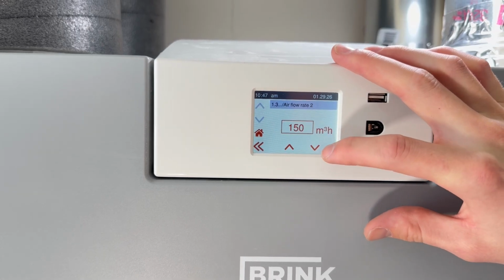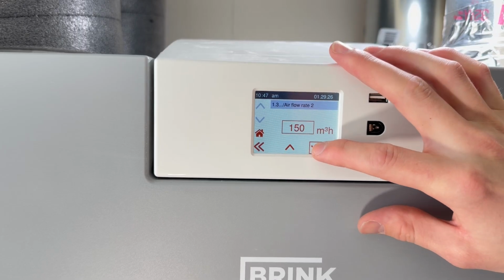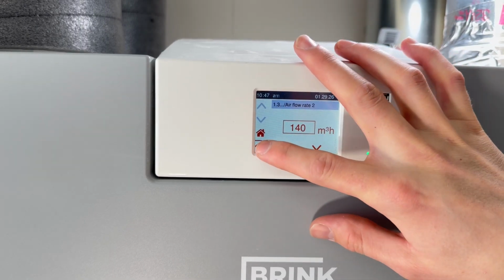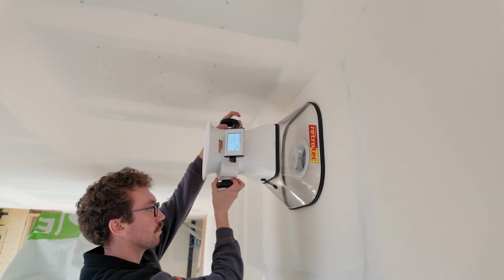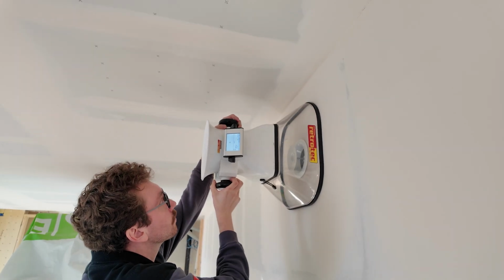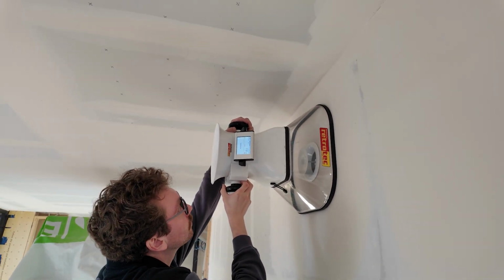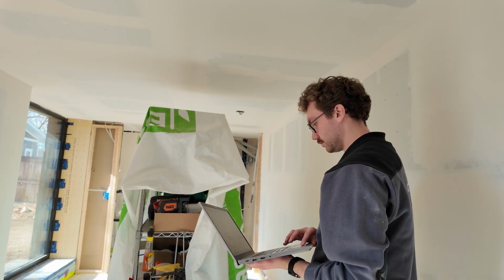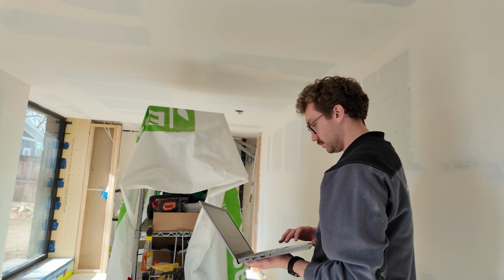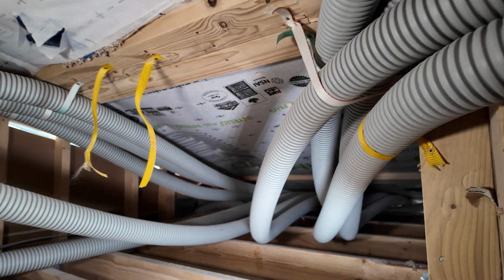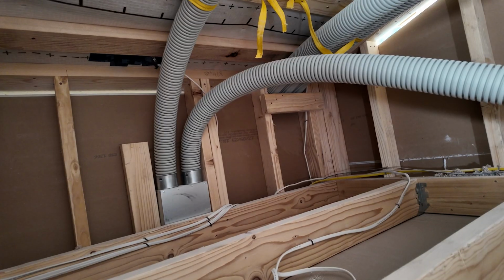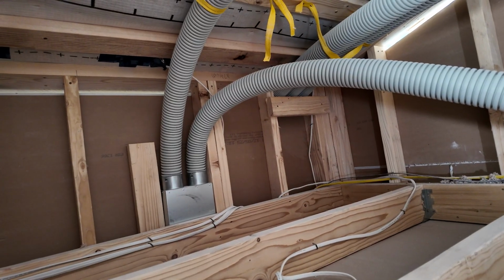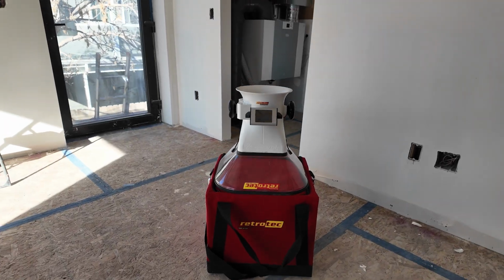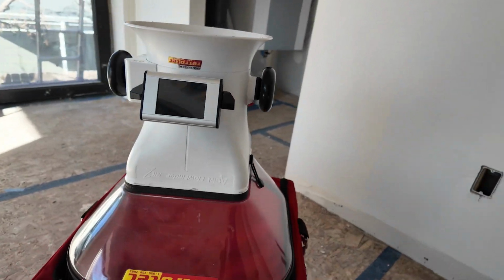While we can be confident in the unit's ability to provide programmed airflow rates, we always advise that systems be commissioned to check that proper airflows are being supplied or extracted from the intended places, and no installer errors were made. For instance, if there's a hole in the ductwork preventing the air from getting to its final destination. We do this with a highly accurate powered flow hood.